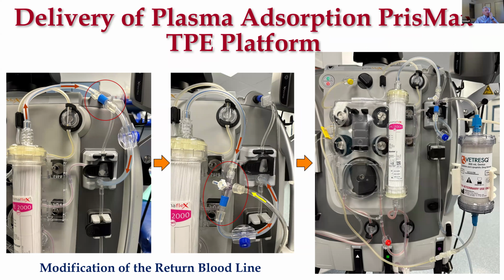So the issue is that we have to satisfy this requirement that whatever comes out of the plasma separator has to be matched by a volume that comes out of the replacement bag, so that those two bags are exactly balanced in the volumes that they're receiving and the volumes that they're removing. And it turns out that an easy trick to do, you have to make a couple of modifications to the system here.